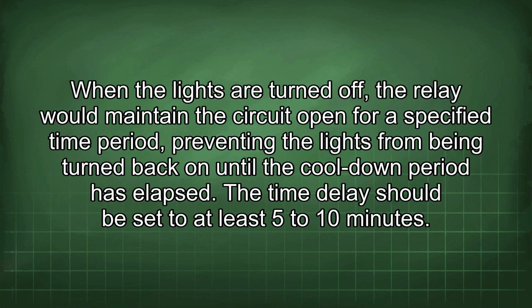When the lights are turned off, the relay would maintain the circuit open for a specified time period, preventing the lights from being turned back on until the cool-down period has elapsed. The time delay should be set to at least 5 to 10 minutes.